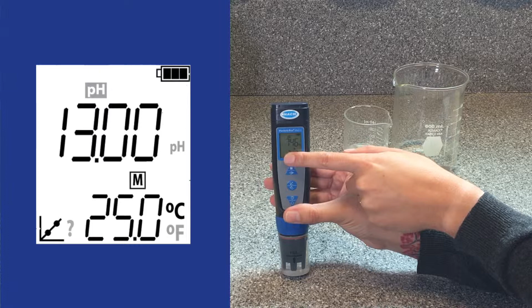One last time, we'll push and hold, and that brings us back to the beginning, which is pH. Keep in mind that the pH may need to be calibrated. Two indications that pH may need to be calibrated is if the pH reading seems wrong. So pH should be in a range of 6 to 8. So if you're outside of that and it doesn't make sense for a water sample, it may need to be recalibrated. Another indication is if the calibration symbol, which is this little graph, pops up in the lower left corner with a question mark next to it. That means it's also time for calibration. So in order to calibrate the Pocket Pro, you're going to need your calibration standards, and then you can either follow the instructions in the manual or watch our separate video on how to do that.